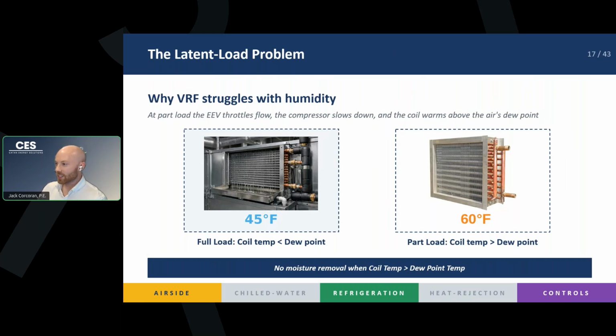And so we're going to get a lot of condensation buildup on our coils. We're going to take the humidity out of the air, and that's really good for latent loads, right? So whenever your coil temperature is low, you're going to condense water out of the air and remove the moisture. However, on the right side, when you're at part load and our compressor speed is low, we're not going to get as low of a temperature at our coil. And the consequence is we're going to slowly drift above our dew point and we're not going to get any moisture removal at our coil. This can be problematic when you have high outside air loads or there's a lot of moisture in your space that you need to remove. If our coil isn't cold enough, then we're not going to be able to remove that moisture.